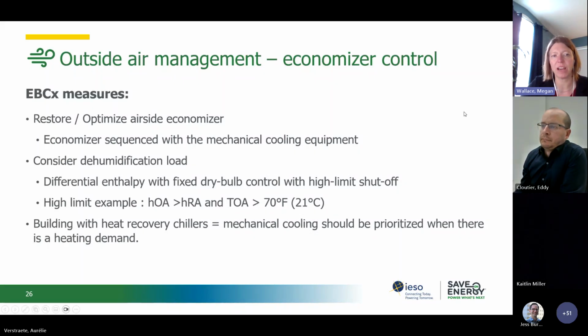So an example of the high limit shutoff would be when the outdoor air is more humid than the return air and the outdoor air temperature is greater than 21 degrees. One thing to note is that in buildings where we have a heat recovery chiller, we want to prioritize the mechanical cooling when there's a heating demand, because that'll be the most efficient choice.